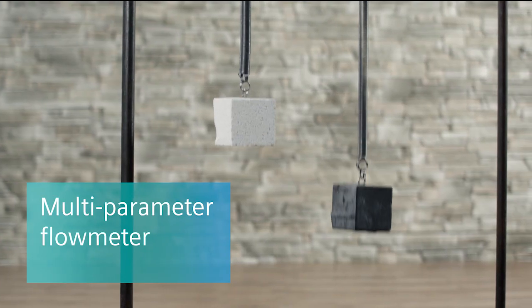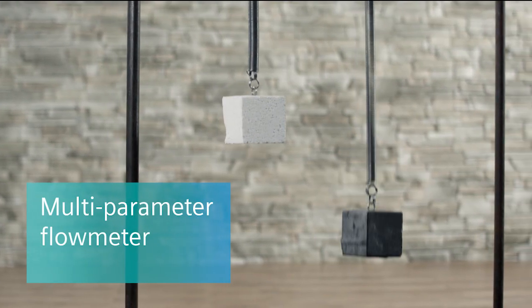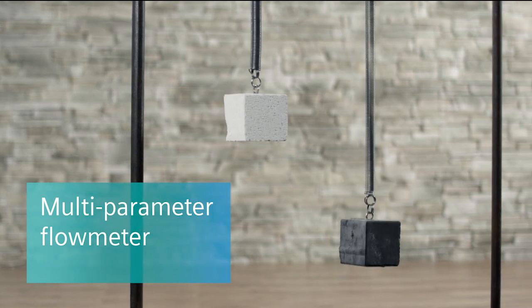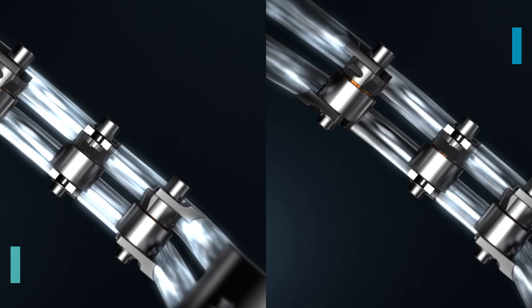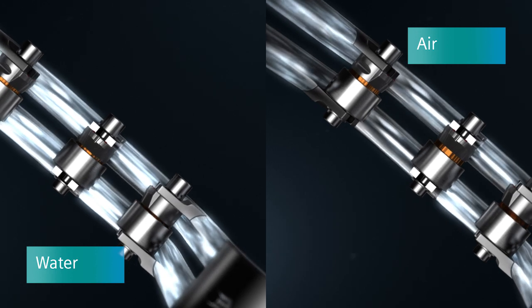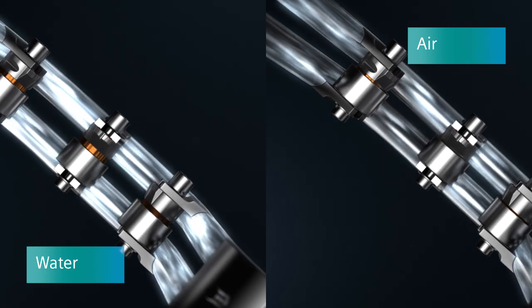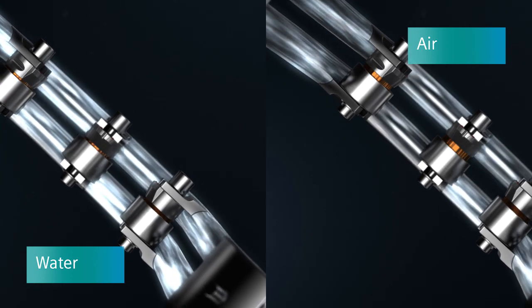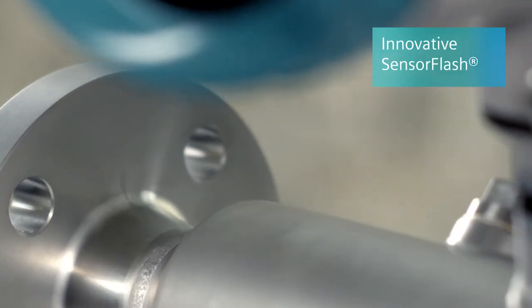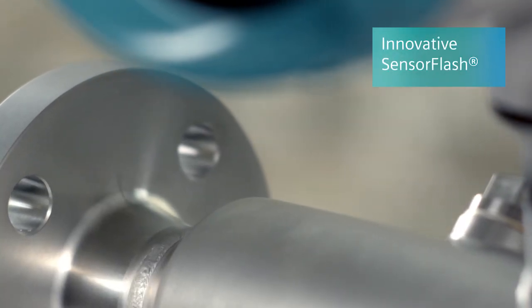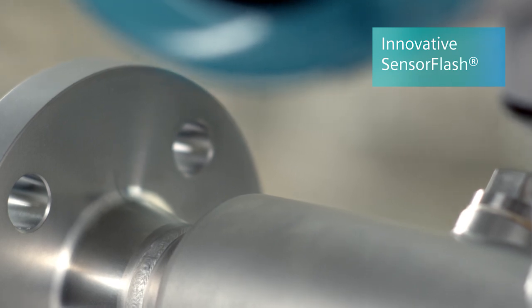In addition to the mass, it determines the density of a medium. Denser media have lower frequencies. Put otherwise, water oscillates at a lower frequency than air. From the measurements, multiple parameters, such as volume or concentration of substances in a liquid, can be derived.